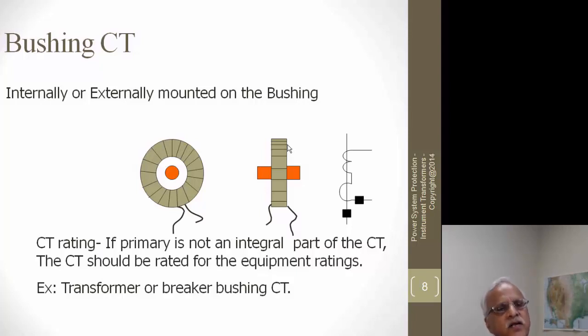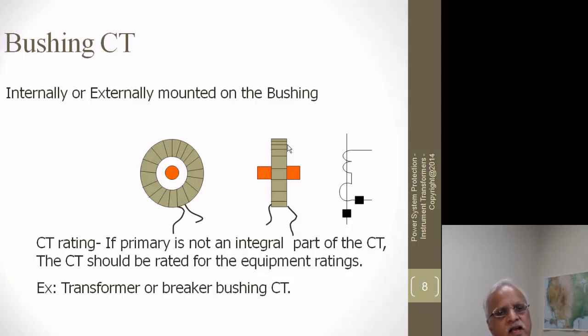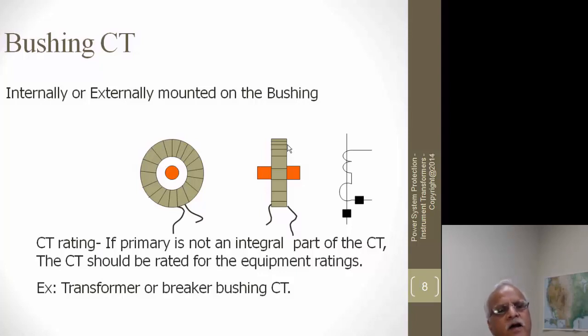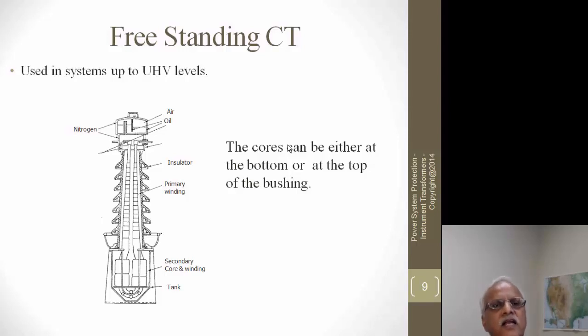The primary rating of a CT is not determined by the CT itself. If it is used on a transformer that can be overloaded to 150 or 160 percent for a short time, the CT must also be able to carry that overload for the same duration. Because the CT is an integral part of that particular breaker or transformer, these CTs must be rated the same as the equipment on which they are mounted.